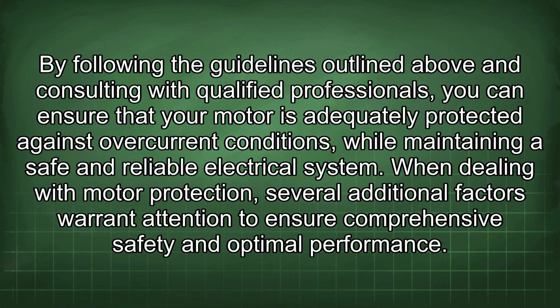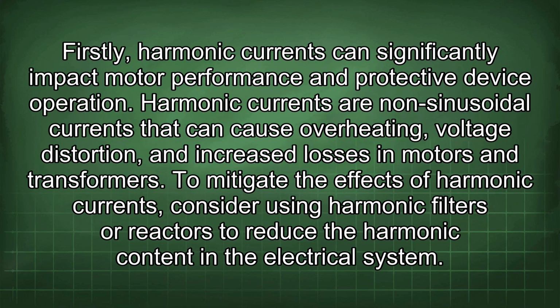When dealing with motor protection, several additional factors warrant attention to ensure comprehensive safety and optimal performance. Firstly, harmonic currents can significantly impact motor performance and protective device operation. Harmonic currents are non-sinusoidal currents that can cause overheating, voltage distortion, and increased losses in motors and transformers. To mitigate the effects of harmonic currents, consider using harmonic filters or reactors to reduce the harmonic content in the electrical system.